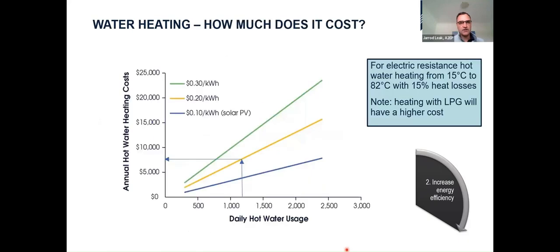To give a flavour here, let's follow the chart again. If you're using about 1,200 litres per day and your electricity cost is 20 cents a kilowatt hour, follow the graph up and over to the right, and that gives a cost of about $7,500 per year just to create hot water, based on your daily usage. A few assumptions: I'm assuming you're heating to 82 degrees from an average of 15. But if you're using something like LPG, the cost will be even higher.